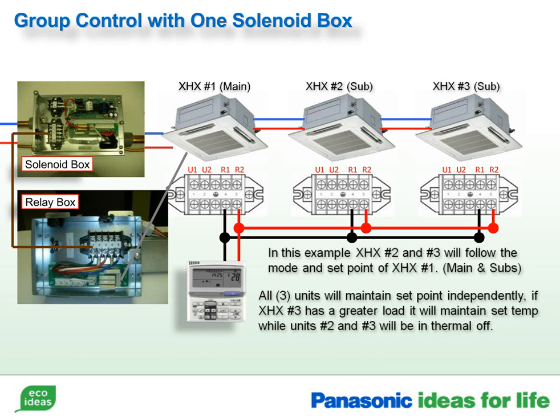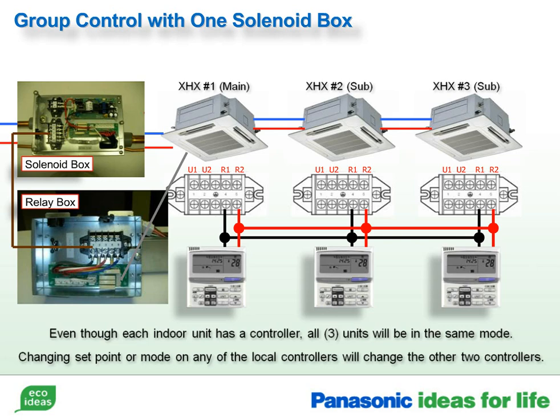These group units will always share the same set point and operate in the same mode. If one of the units achieves set point, it will go thermal off, but the other units will continue to run until they reach set point. A good application for this would be a conference room or a large common area. In this example, each unit has its own local controller. An input made to one controller will change the others. The same rules apply, whether you have one controller or multiple controllers. They will all share set point and mode.